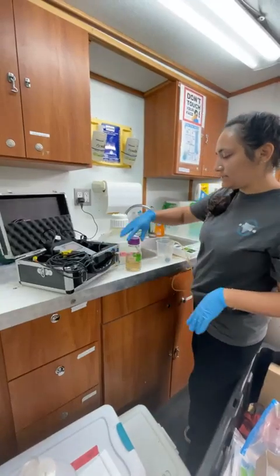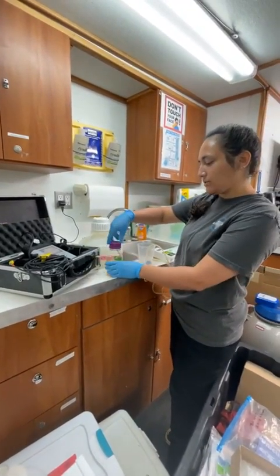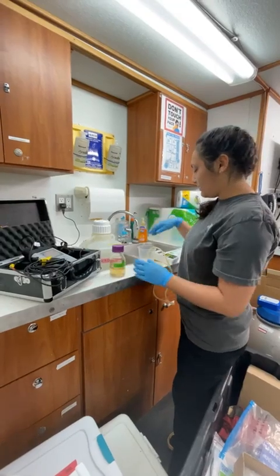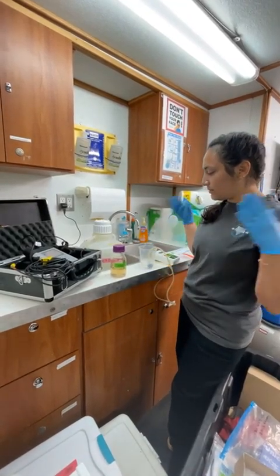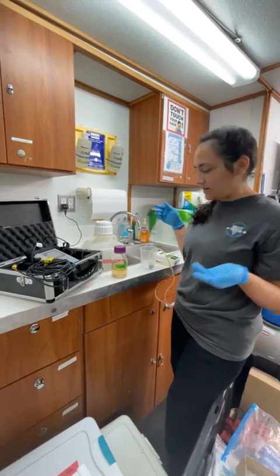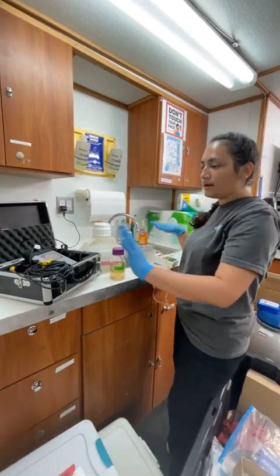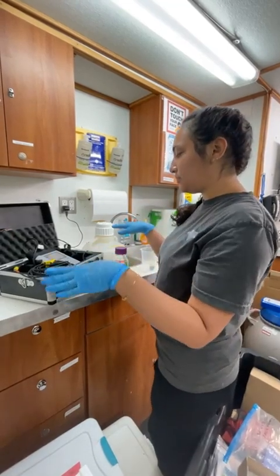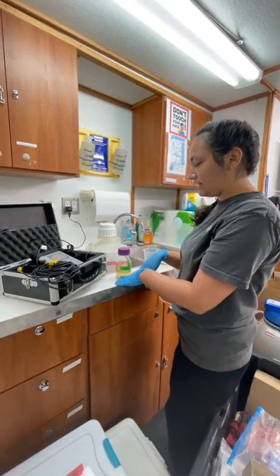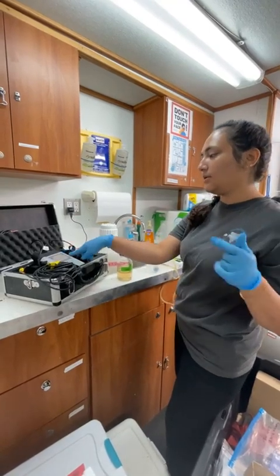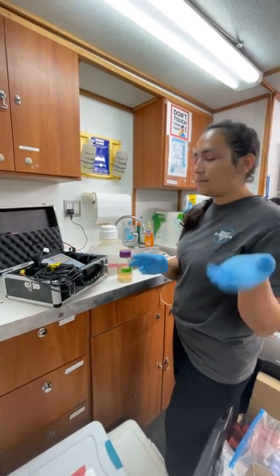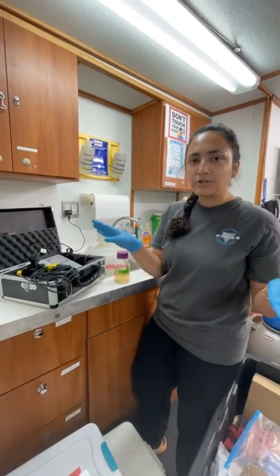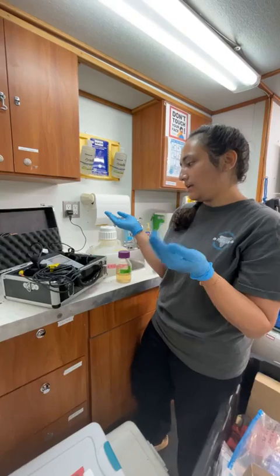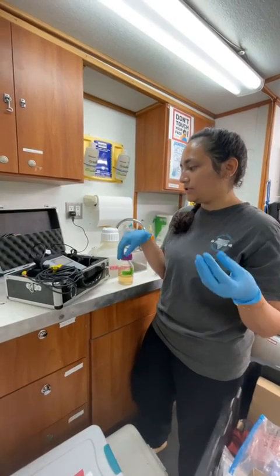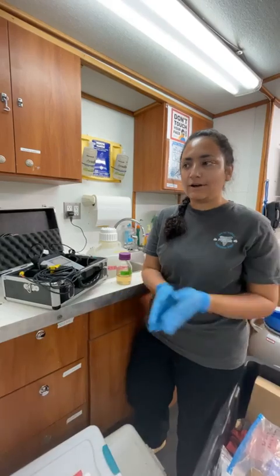So I'm calibrating right now, and this is basically the low calibration, or cal 0. And then this is the high calibration, because it is a bubbler, so it's getting aerated and oxygenated. So this is our low and high, and I just put the temperature probe and the oxygen probe inside each of these, and then take the measurement, and then the machine saves that calibration information. Then when we use the sensor in our sample, it uses the calibration to tell us the concentration of oxygen.